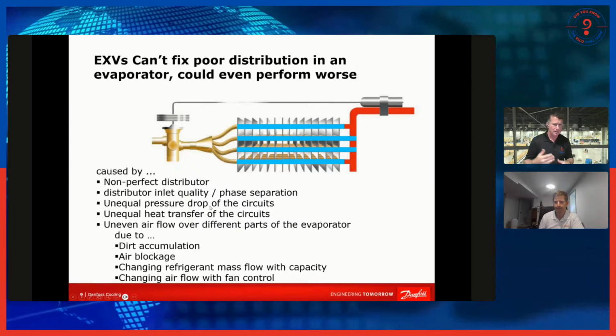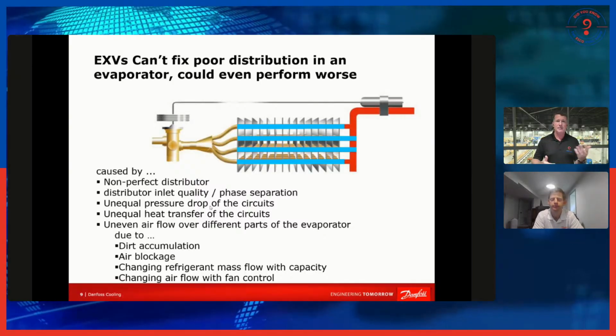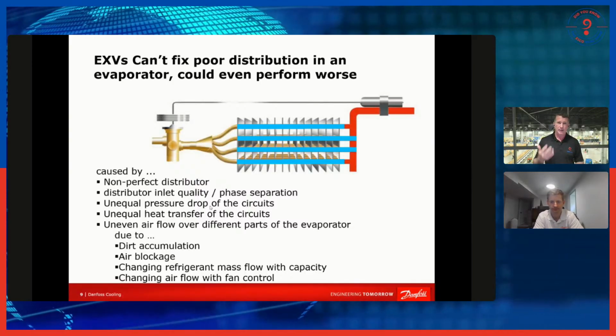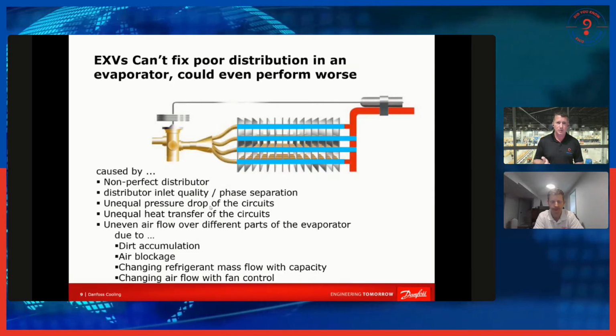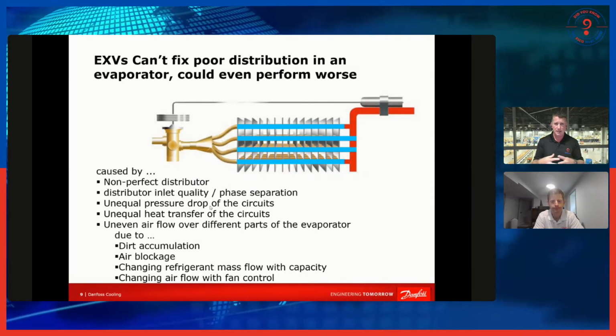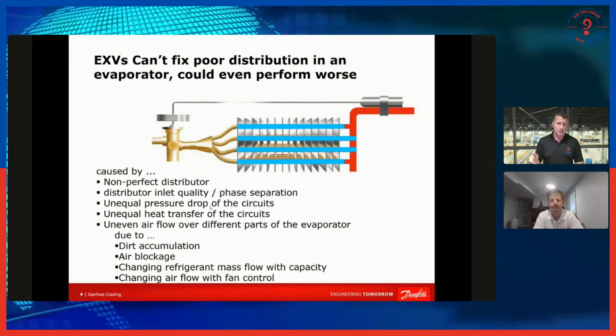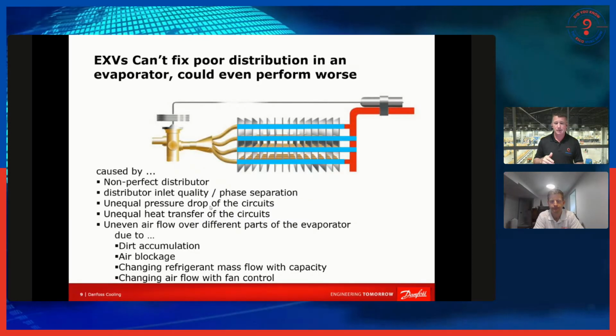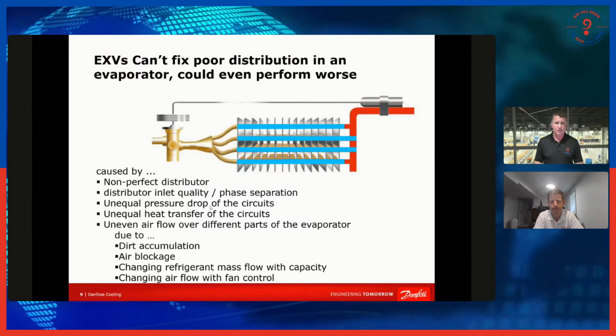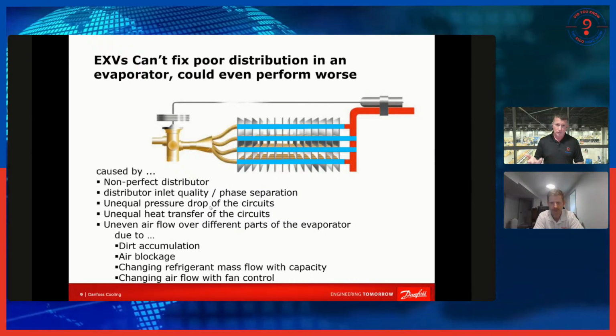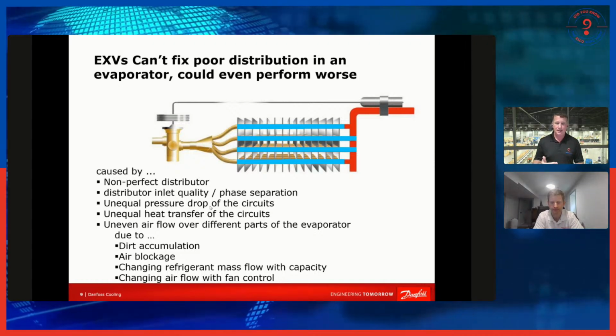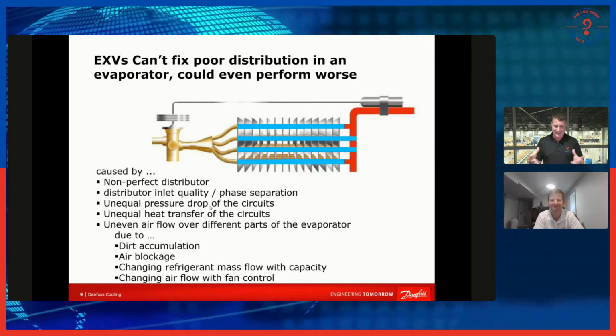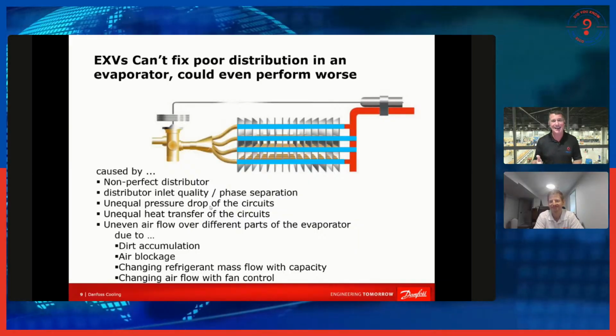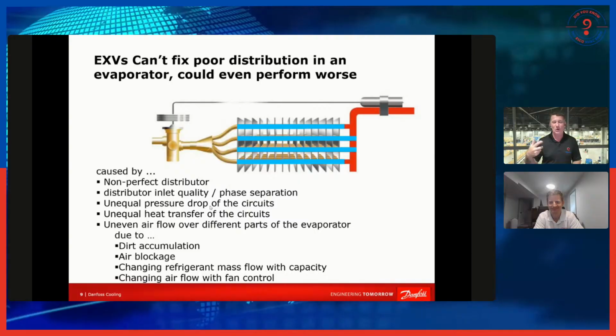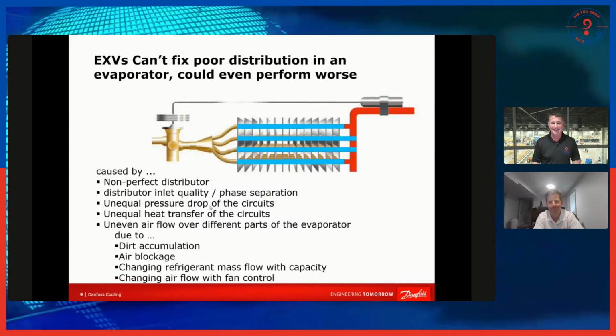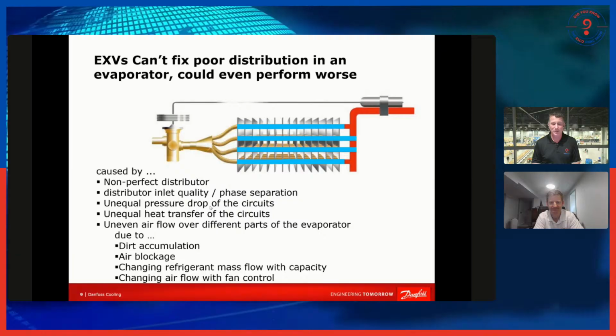I'll get questions on this every once in a while of, what kind of scenarios could we see something like this? Well, here's an example I use all the time in the Midwest. In Indiana, where I'm from, a lot of our installations are counterflow. They're downflow furnaces with a coil underneath of the furnace. And because in the wintertime it gets very dry here, we add a bypass humidifier. Now, since we don't have ductwork to tie our bypass into, we'll cut a 6-inch hole in the side of the evaporator case, and that is where our bypass line connects from the humidifier.